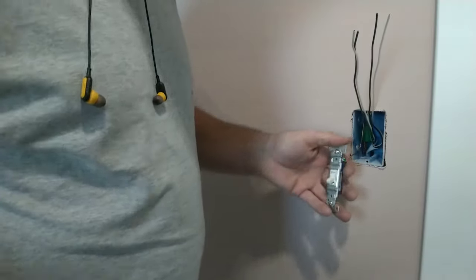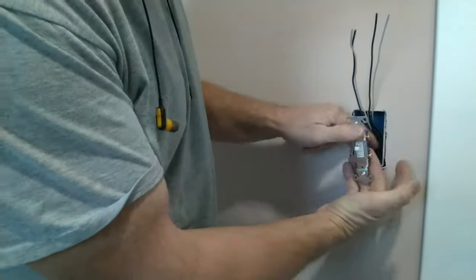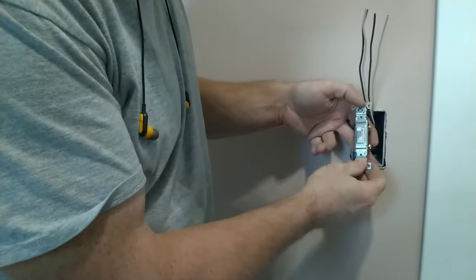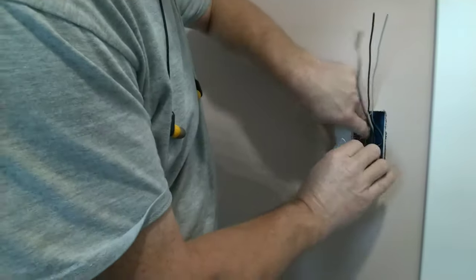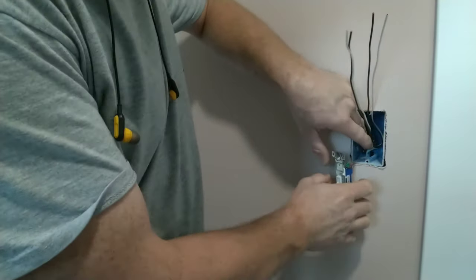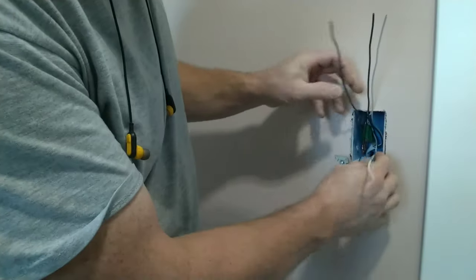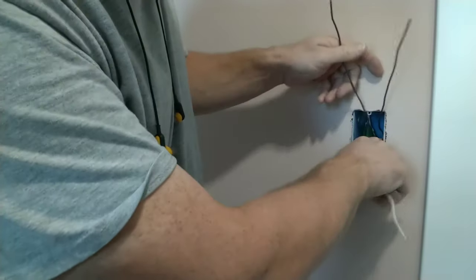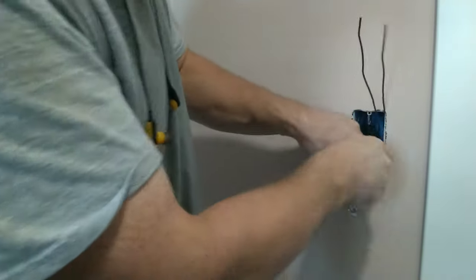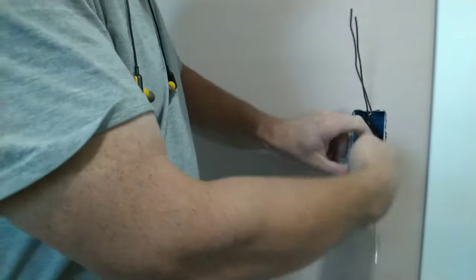Now the switches that I buy always have the grounds on the bottom. This is an Eaton 15 amp switch. I never use the stab locks in the back. They're more of a fire hazard than anything. Take your neutrals, pull them down to the bottom corner of the box, and start twisting them.